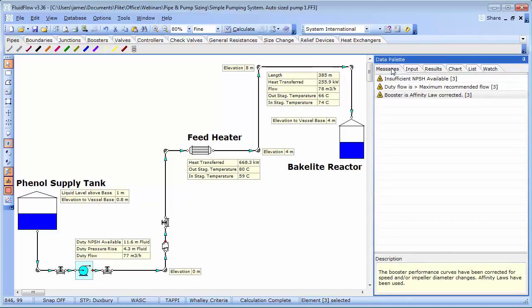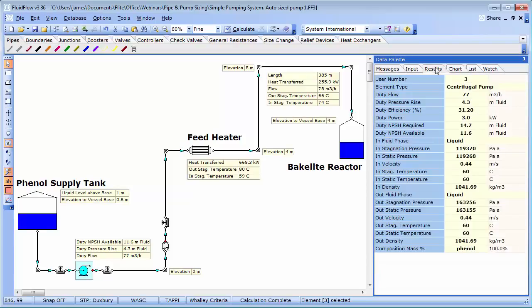The warning is advising us that the NPSH available is insufficient to meet the needs of the pump NPSH requirement. Let's have a look. So we have 11.6 meters of fluid available, and we have a requirement of 14.7. So we have a problem.